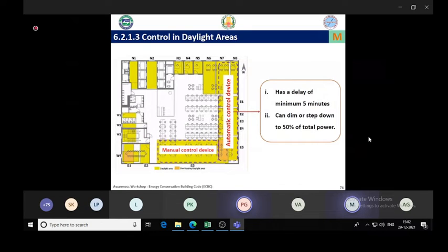Now, in daylight controls, in a building or a space, whichever areas are complying with daylight criteria, in those areas it is mandatory to have daylight controls. So it could be manual or automatic. If it is manual, then we should be able to manually switch off 50% of the installed lighting, and this should be distributed evenly across the daylight space. So either it can be a dimmer or it could be switches, ideally dimmer. If it is an automatic control, again, we have to have a dimmer to reduce the overall illuminance, or it could again switch off 50% of the light fixtures, depending on the lighting level.